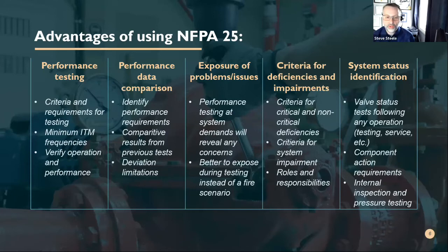So the more you do work these systems as far as routine maintenance or testing, that valve status, that is absent in the Ontario Fire Code as it is now, regardless of what you ask or require to be performed on that system. The valve status test is one of the most important things on there, and that comes with the training and the competency of those doing the work. Anybody can turn a valve. You can show somebody, okay, you close the valve, you open that valve, you've verified that it has worked. But with that comes a burden of responsibility.